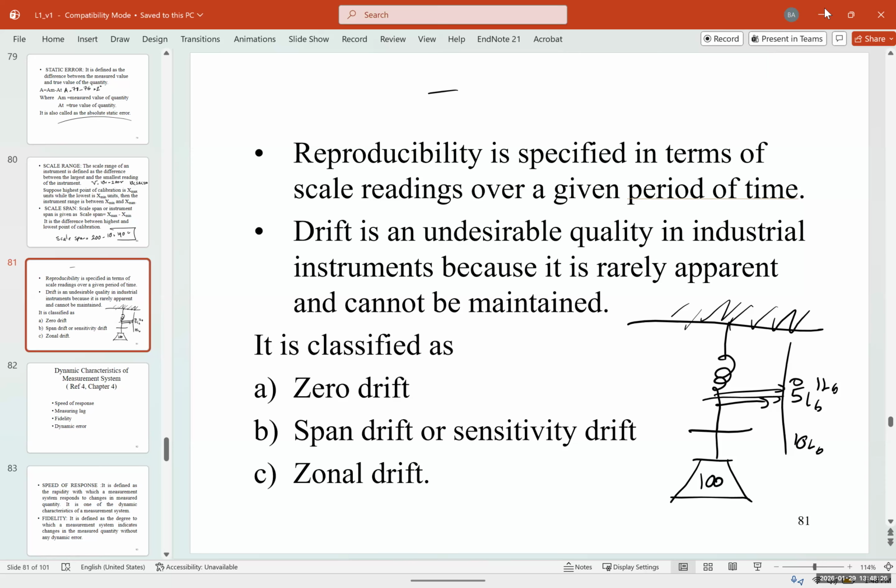And this happens for a lot of measurement tools. Even I have seen this in the tools that they have in the labs for measuring, doing blood work, measuring glucose or cholesterol or something like that. They have to be calibrated every day because they have drift.